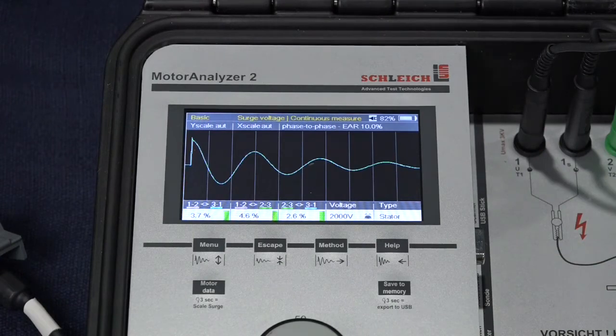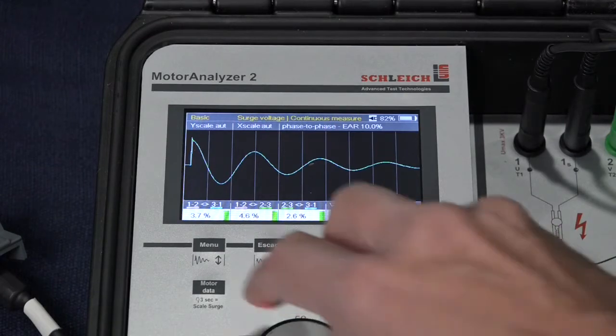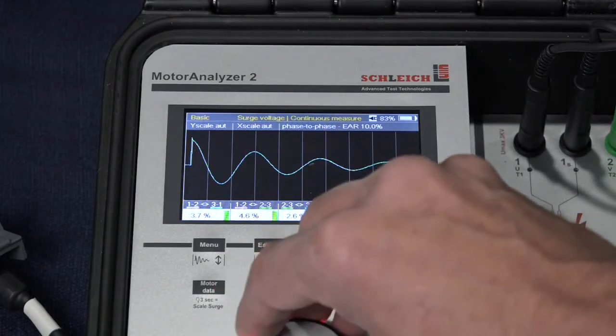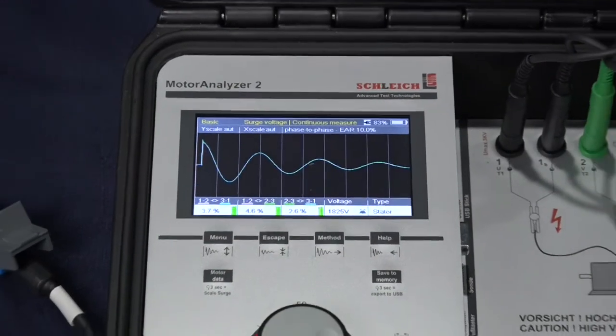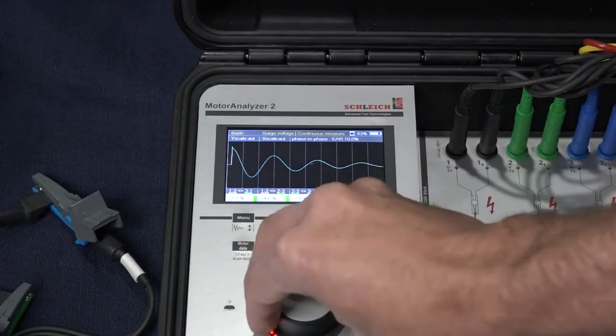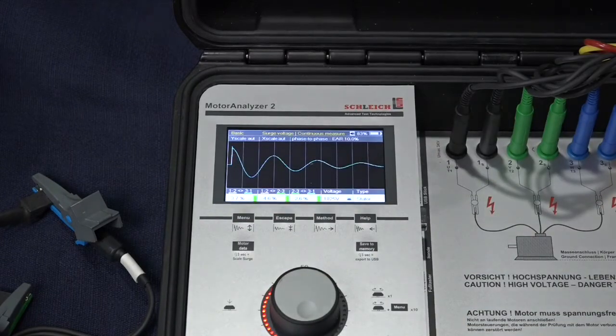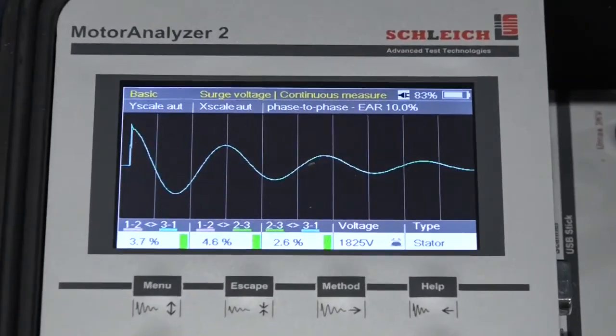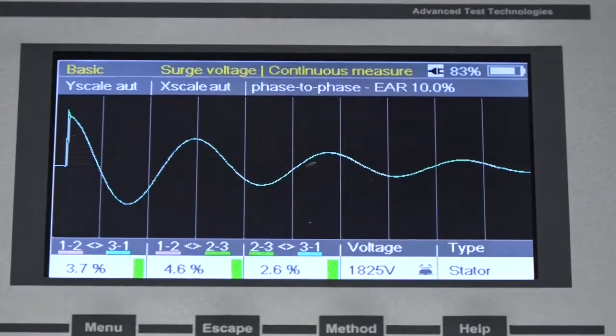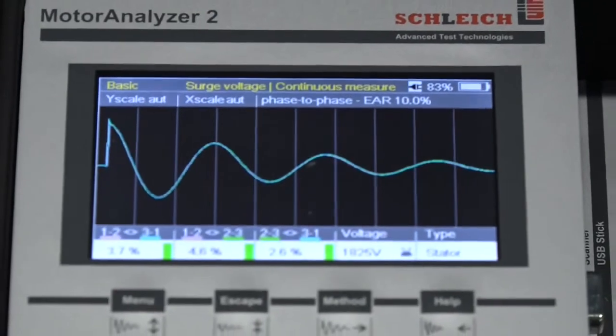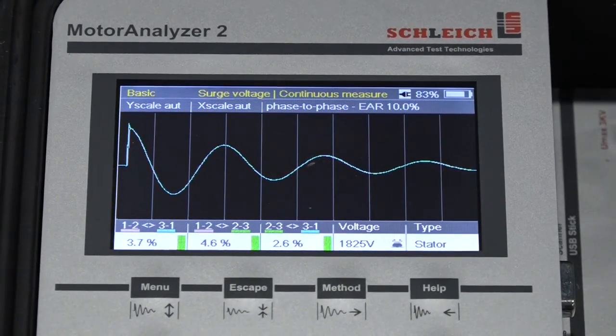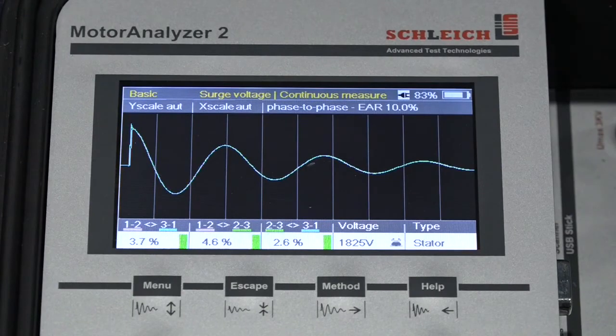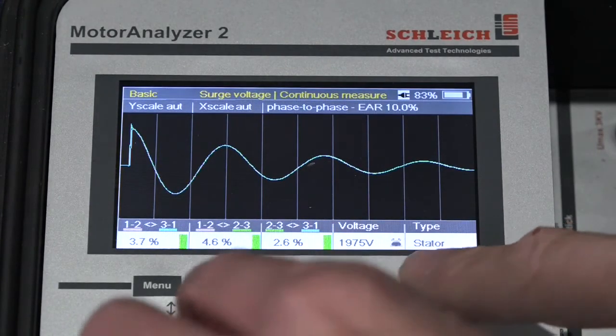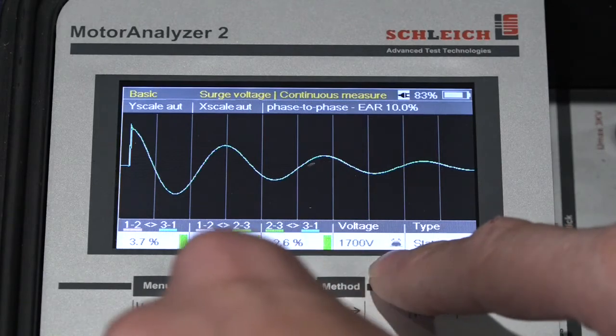When we test the stator by itself, we can manually operate the tester. Here we can see by moving the whiz wheel back and forth, I can change the test voltage. Now, it's not going to let me exceed 2,000 volts, which is the recommended voltage for testing a 480 volt winding. Let me get you in there so you can see. Here you can see by moving the knob we can change voltage up to 2,000 volts.